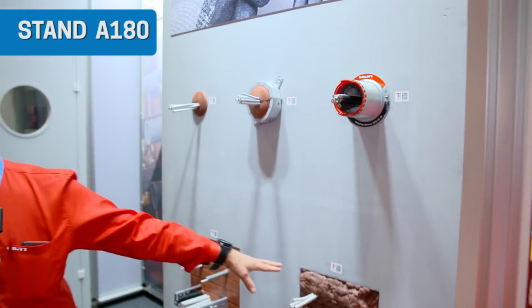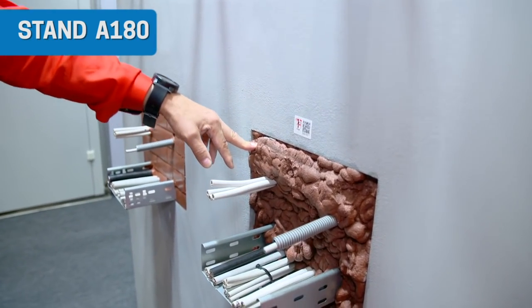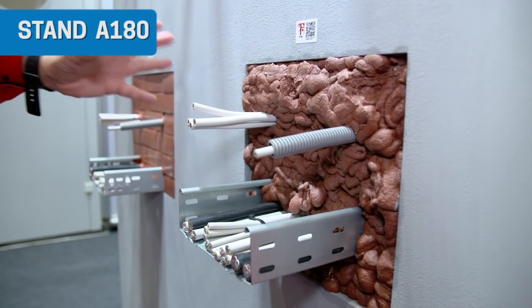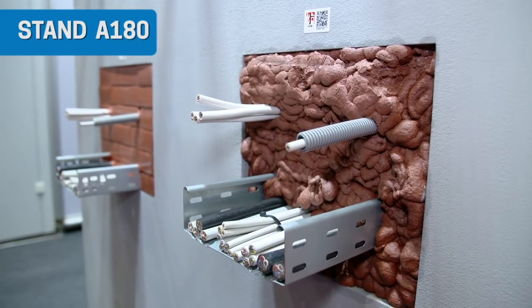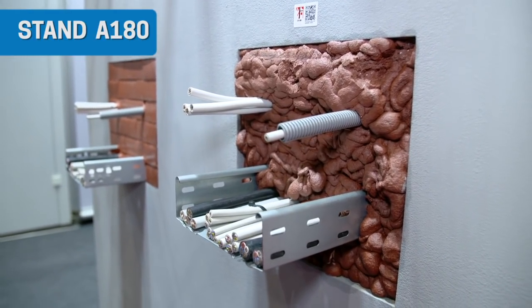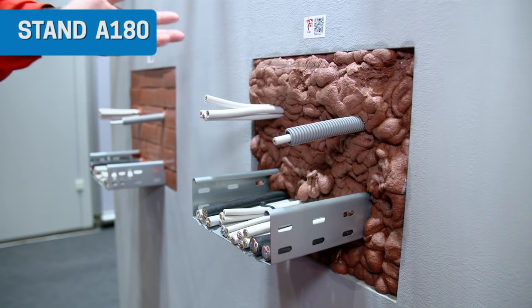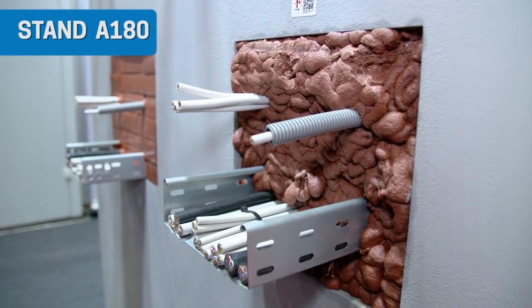What products do you want to showcase? In terms of retrofit, a lot of these products are used. For example, this one is an injectable foam, which is used to seal around cable trays, pipe penetrations, and multi-service openings. It's a big advantage as it can all be done from one side. It's very quick — takes about 20 minutes to cure. That's it, you have almost an instant fire stop.